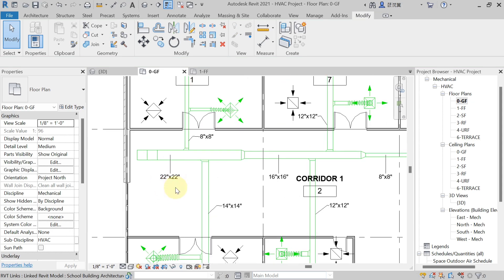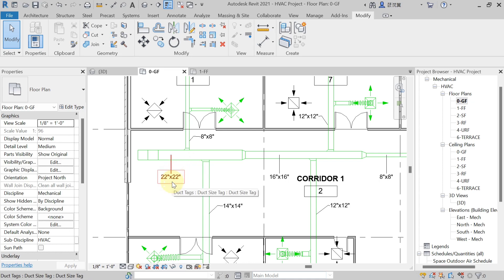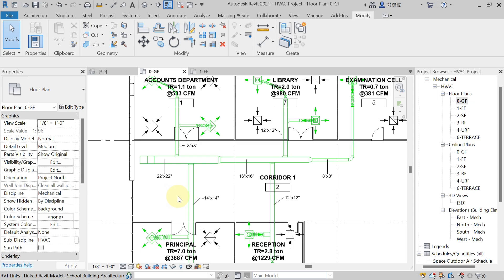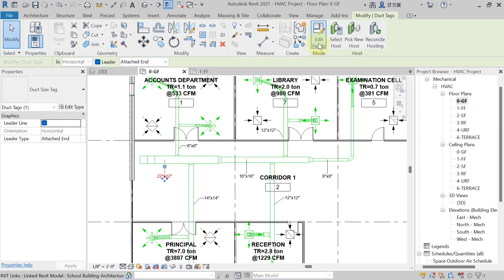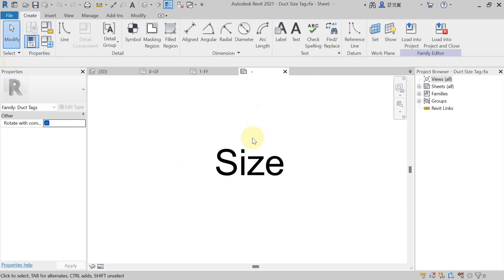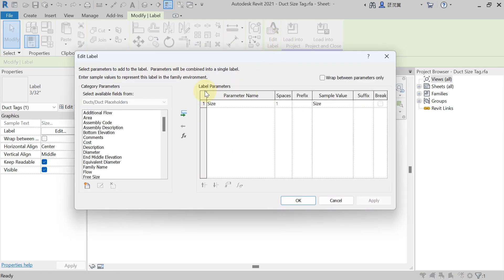Right now the tag is only showing you the size of the duct. Suppose in this tagging you also want to see the bottom elevation of duct, and the airflow value. For that, select the existing tag from the drawing, go to the Modify tab, Mode panel, and hit Edit Family. Now select the size label and hit Edit Label. In this label, only the size parameter is added, which is why only duct size is visible in your tagging.